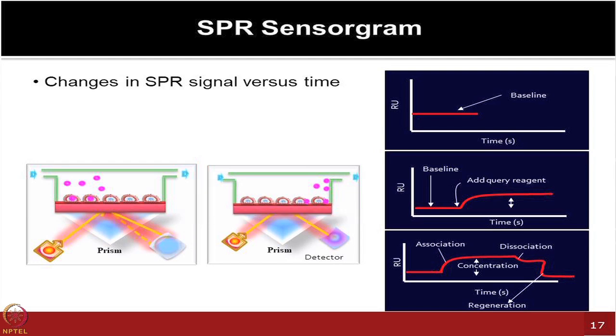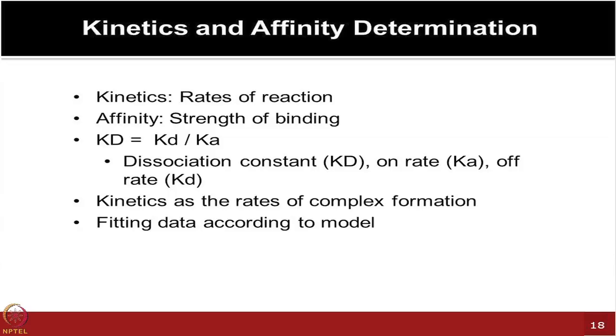Since the experiments are done on noble metals — essentially gold — which are costly, you want to regenerate and reuse the same slide. You use mild acids to strip off the bound molecules without disturbing the printed capture molecules, wash with buffer, and the same chip can be used again for the next round of interactions, reducing cost. This platform offers powerful information: you get kinetics, the rate of reaction, and can monitor on-rate and off-rate in a label-free, real-time manner.